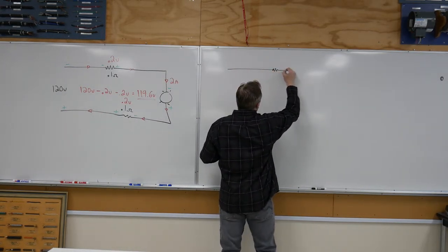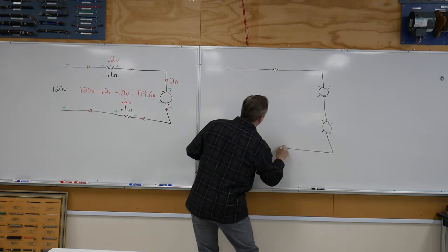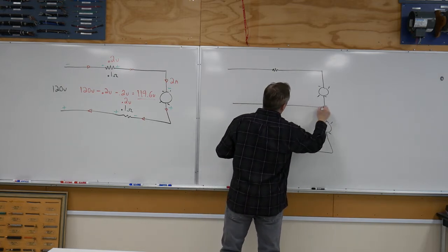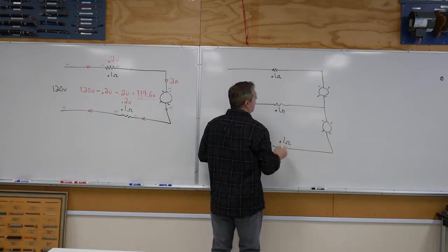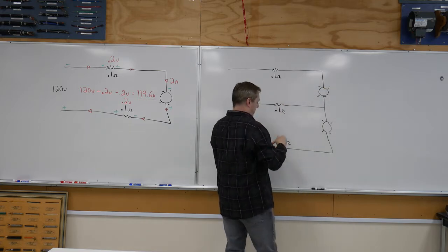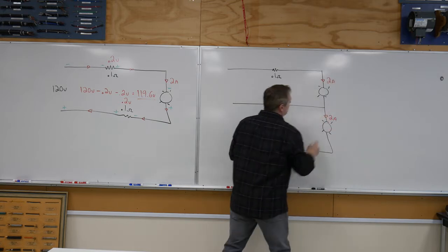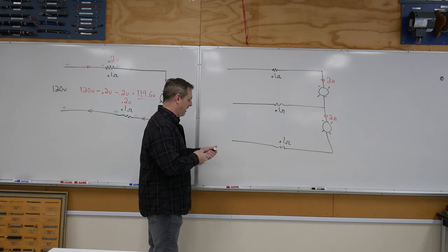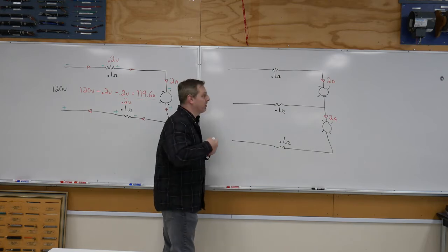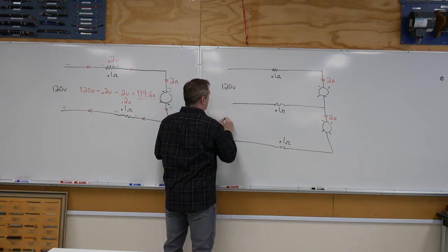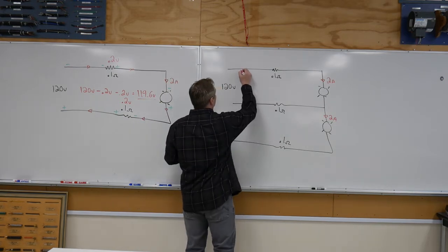All right, so if we looked at a balanced three-wire circuit, still with our 0.1 ohms on each of our line conductors, and I'm going to say that each of these loads is drawing the 2 amps. Because each of those loads is drawing the same current, it's fair to say that our neutral will not contain any current on it. We're going to start with a source voltage of 120 volts. We're going to analyze the direction of current flow within here.